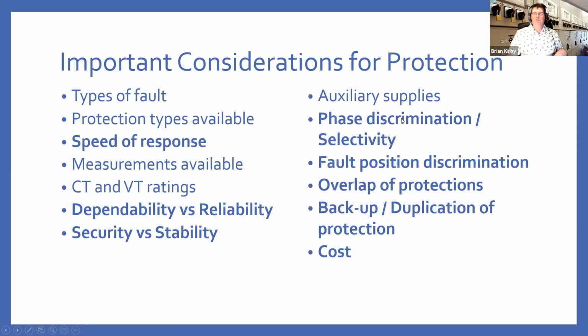We need to be able to do discrimination of phase. So if you have a single phase fault, you need to be able to identify that and select that phase for individual operations if that's what the customer wants. You also need to be able to work out where the fault is, particularly on long overhead lines, because you may need to send someone out to investigate what's going on. If you've got multiple zones of protection, you want to make sure they overlap so that there are no blind spots.